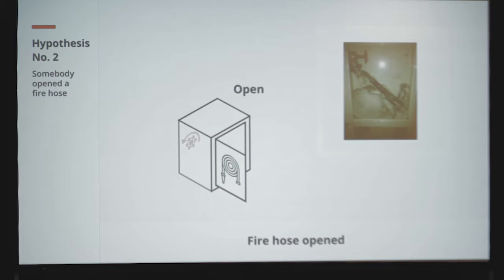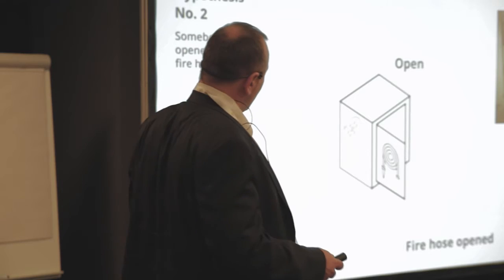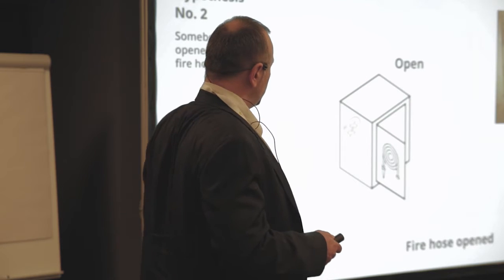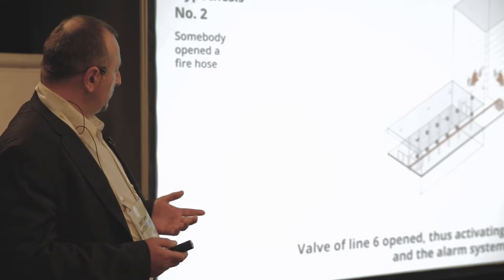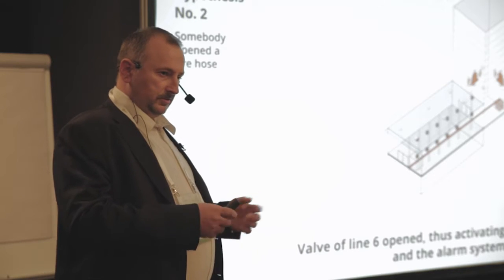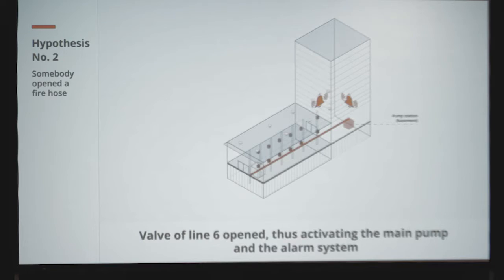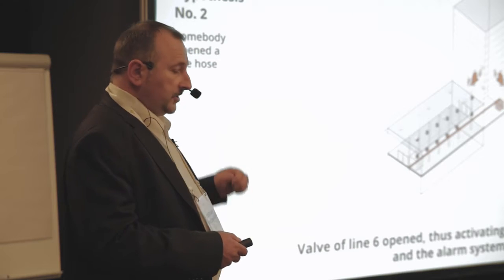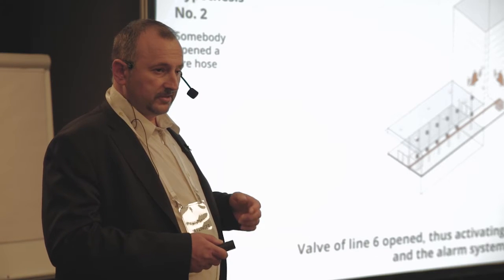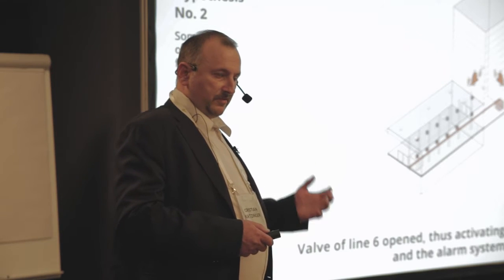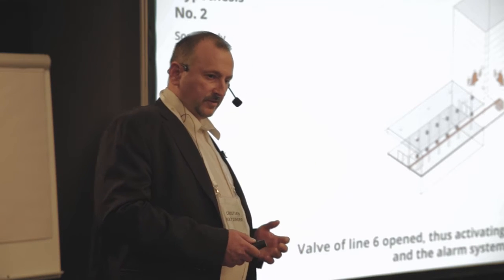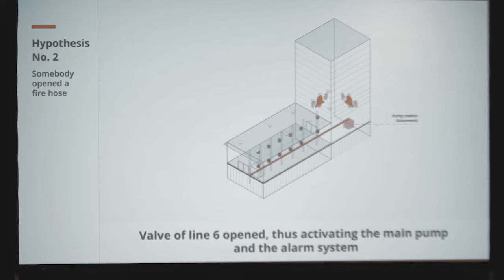Another possibility: we saw that there's an open fire hose cabinet, and we see that there's some disruption here. So there could be the possibility that someone dismounted the rope of the fire hose from the valve and opened the valve, perhaps to get water. That could be a possibility, but that's speculation, we don't know. They opened the valve, and of course there was a very fast drop in air pressure. And this cabinet is nearer to valve 6 than valve 5.